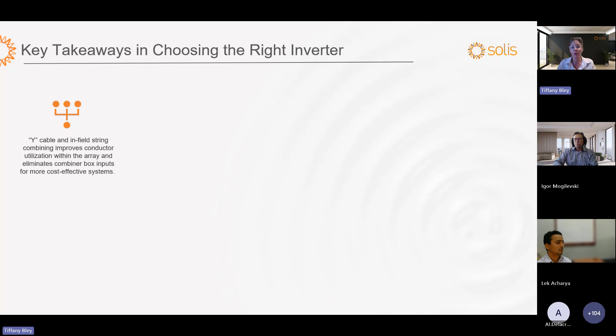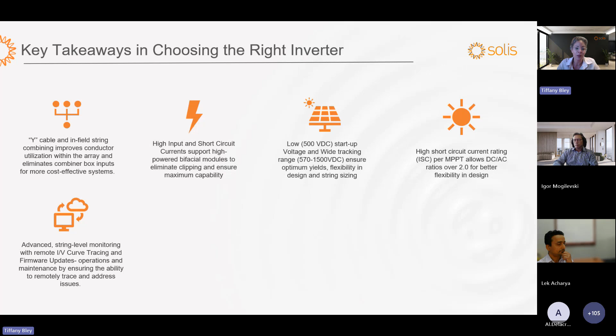High input and short circuit current support high-powered bifacial modules to eliminate clipping while ensuring maximum capability. We have a low 500-volt DC startup voltage and wide tracking range, which ensures optimum yields and flexibility in design and string sizing. We talked about the high short circuit current rating per MPPT, allowing for that high DC to AC ratio. The advanced string level monitoring with remote IV curve tracing and firmware updates helps operations and maintenance and ensures the ability to remotely trace and address issues if there's a problem at the site.